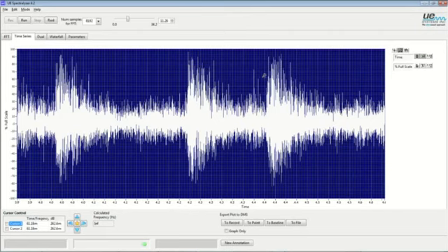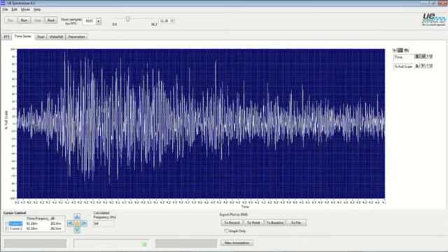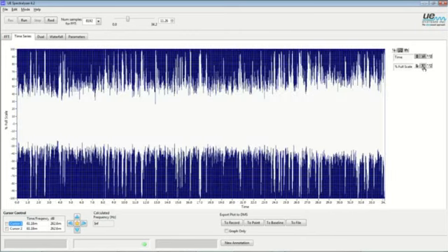If we gauge severity on a tracking event, we want to look at how often the discharges are occurring and how frequently, because no two tracking events are exactly the same. They are very different in how severe they are. It depends upon the type of insulating system, the operating voltage, things of that nature. But it becomes worse when we see this increase in the number of discharges taking place and how frequently that is taking place over the time of the recording.